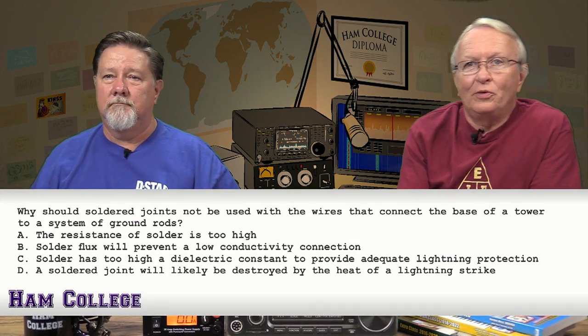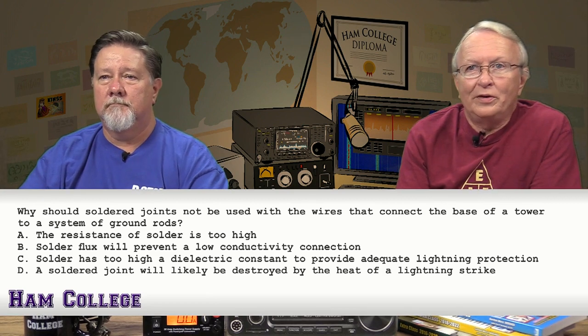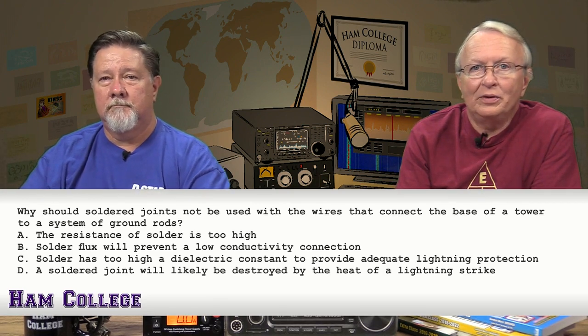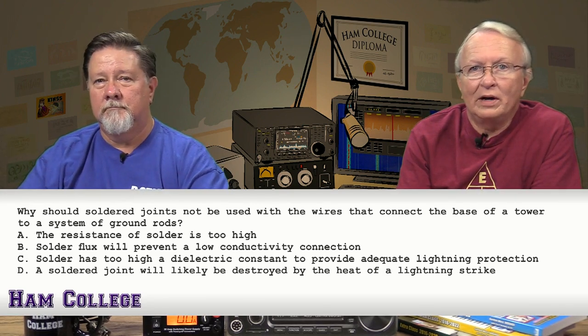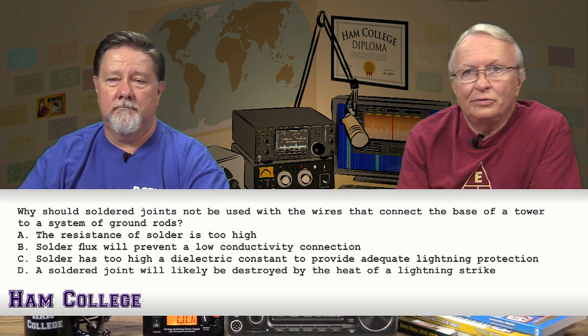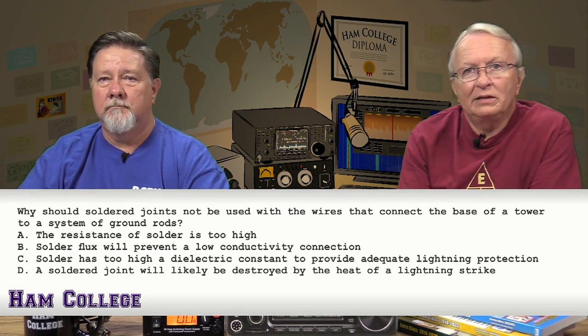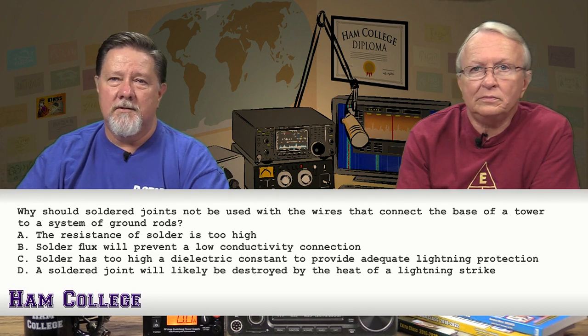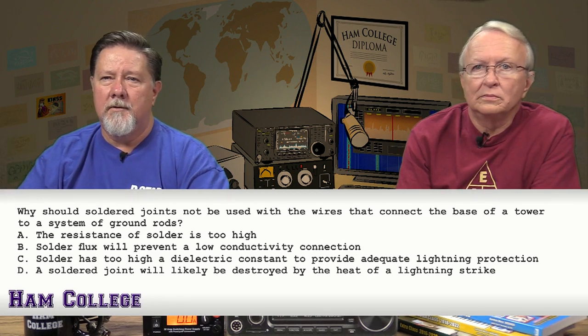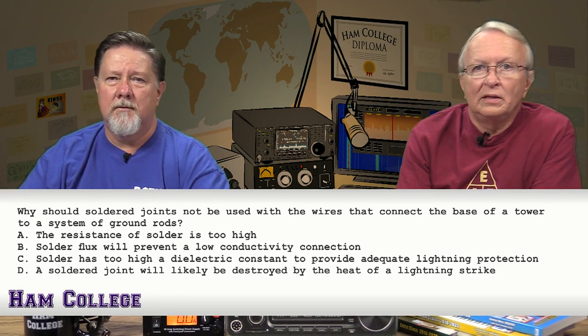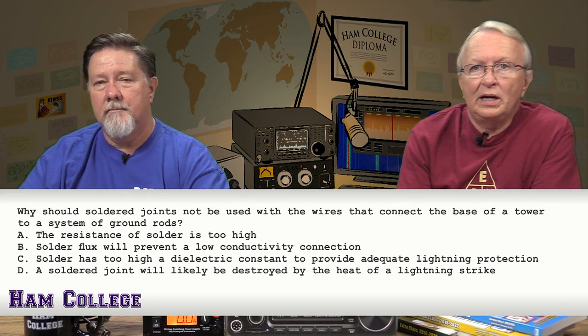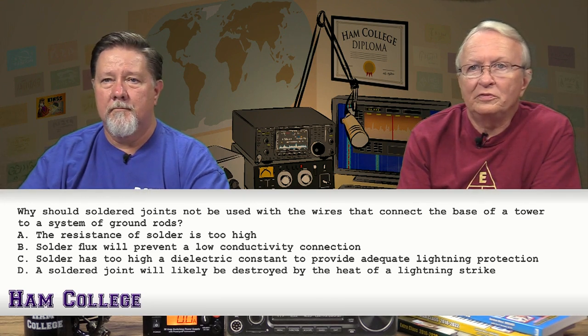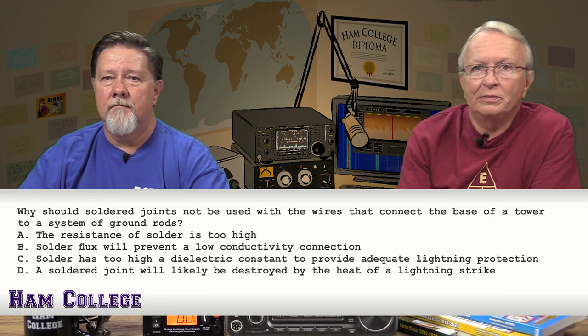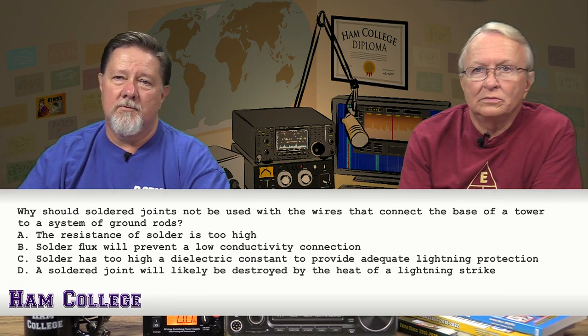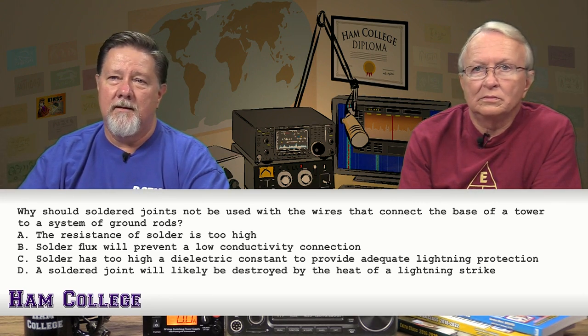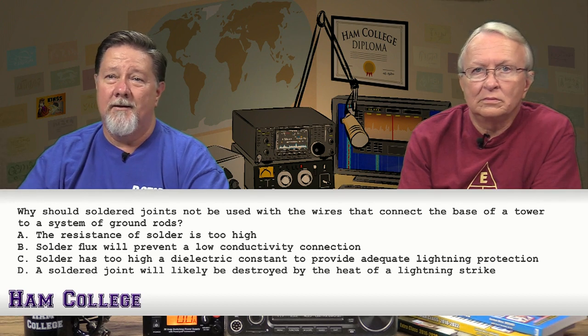Why should solder joints not be used with the wires that connect the base of a tower to a system of ground rods? A, the resistance of solder is too high. B, solder flux will prevent a low conductivity connection. C, the solder has too high a dielectric constant to provide adequate lightning protection. Or D, a soldered joint will likely be destroyed by the heat of a lightning strike.